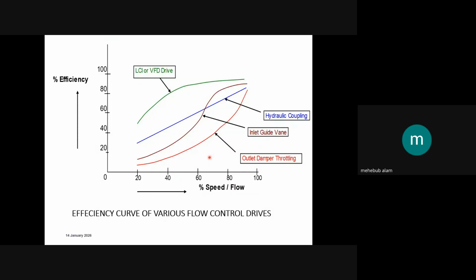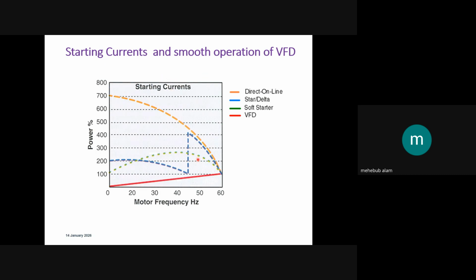Now, the operating principle of VFD. As you know, there are many speed control mechanisms, like outlet damper control, inlet guide vane control, or hydraulic coupling control. A VFD drive has a very high efficiency compared to those other speed control mechanisms, and for that the choice of VFD is justified. The current drawn by the VFD is smooth in nature, lower, and there is no fluctuation. But in the case of starting current, there will be fluctuation, so the mechanical stress on the drives will be more. That is why the VFD is a very popular choice in any power industry.